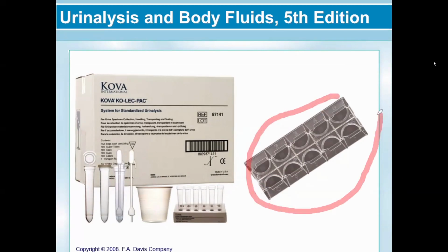So if you can see, this special slide has 10 slots, so we can process 10 specimens in this specialized slide. In the middle, guys, there's a square portion. That is the mid portion of our counting area. It has a grid similar to your hemocytometer. The area of this is usually 3 mm by 3 mm. This is where we examine under the microscope.